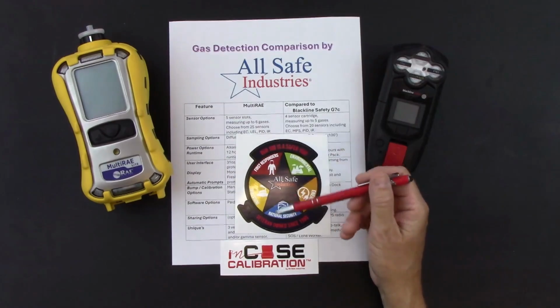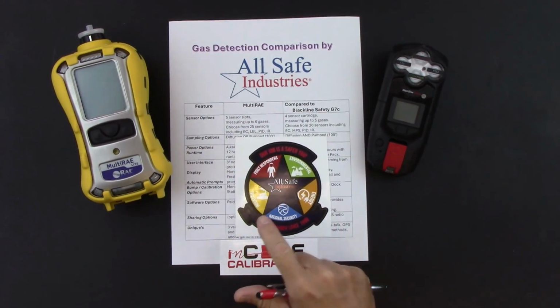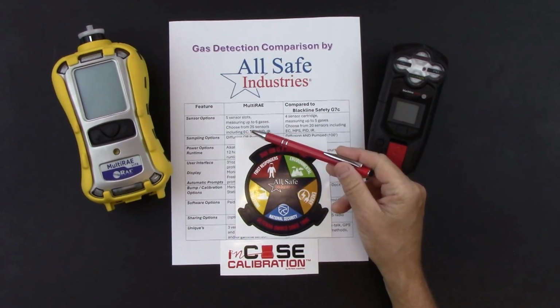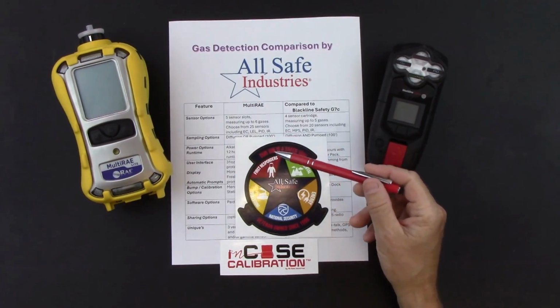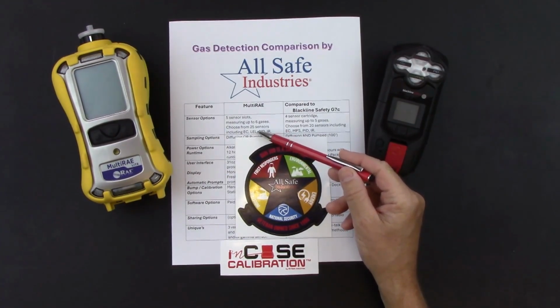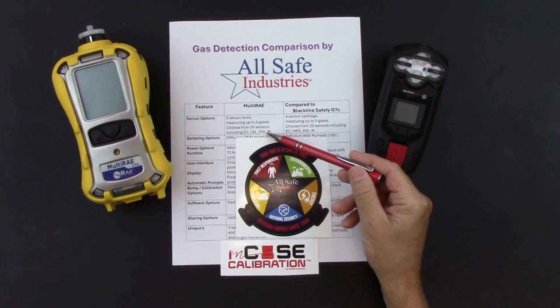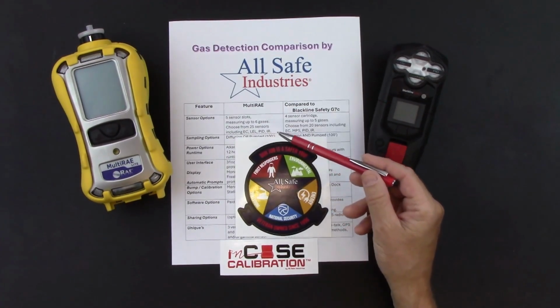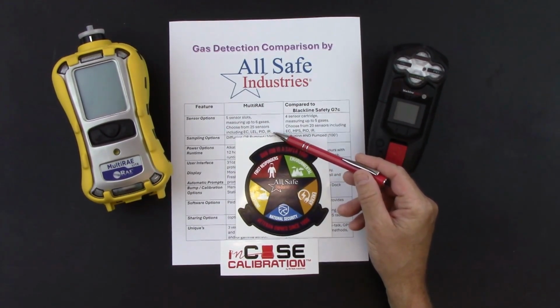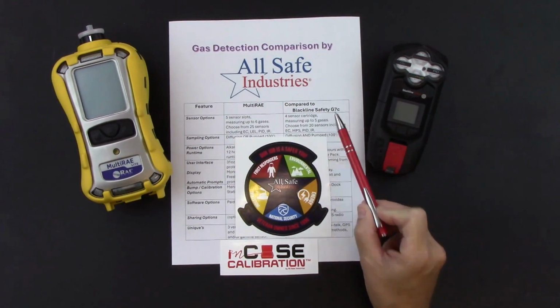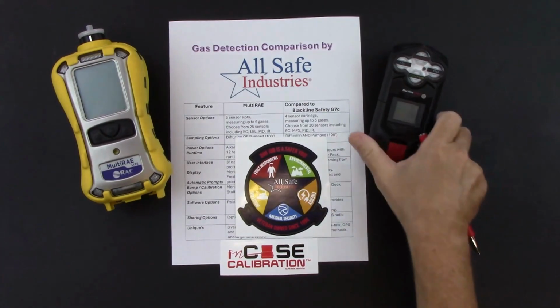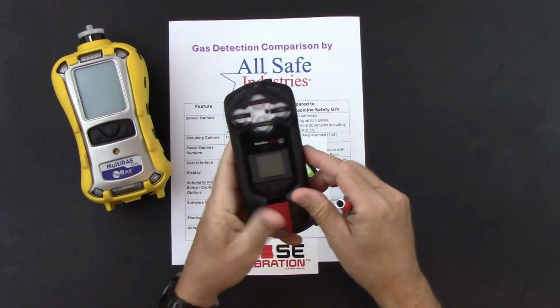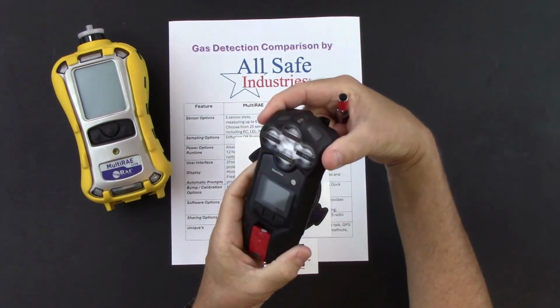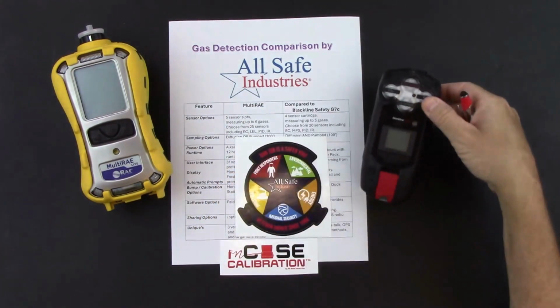We have 25 different sensors that we can choose from, and those include electrochemical sensors for oxygen and some of your toxic gases, a catalytic bead LEL sensor, a PID sensor in 4 different lamp powers, and an infrared sensor either for combustible gases or carbon dioxide. For Blackline Safety, the G7c, we use a sensor cartridge, so not individual sensors. You can see 2 screws on the side of the meter hold this sensor cartridge. This is one complete assembly that you would order from the factory.